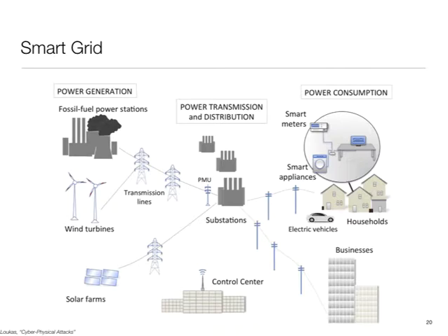phasor measurement units, are getting inserted in a variety of places. What these PMUs do is continually monitor, at that point in the grid, the flow of electricity. In effect, they monitor the AC current and the AC voltage. That's what's called a phasor: what's the phase, what's the amplitude? You have three voltage phases and three current phases, so you're measuring those vectors.